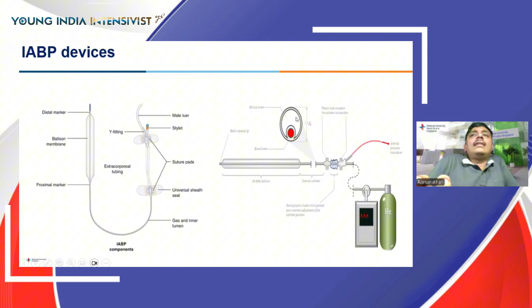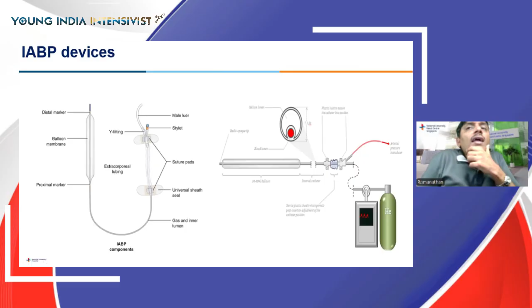So clearly, this particular sheath is introduced through this catheter. And if you look at the cross section of the balloon, this is how it looks. So the helium surrounds the blood lumen. So essentially, this has a transducer which you can transduce, and you can detect the patient's arterial trace. Now, the balloon can be sized depending upon the patient's height.